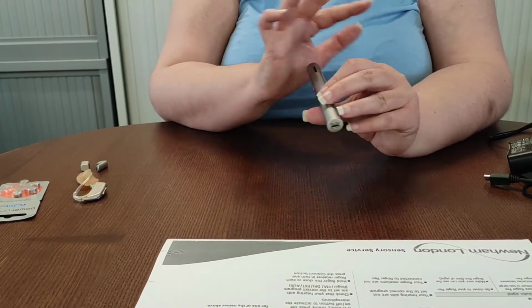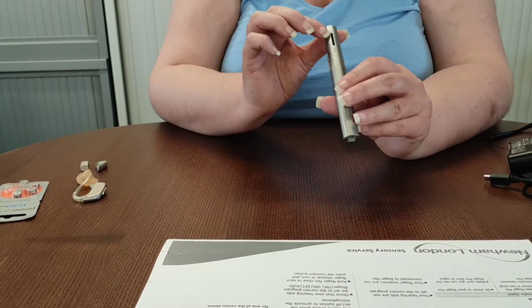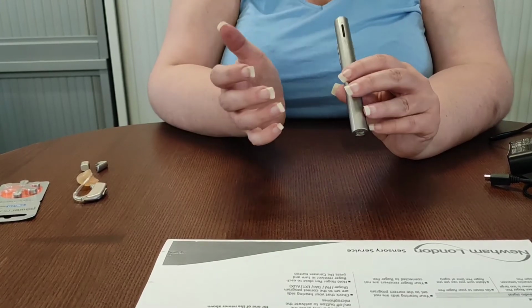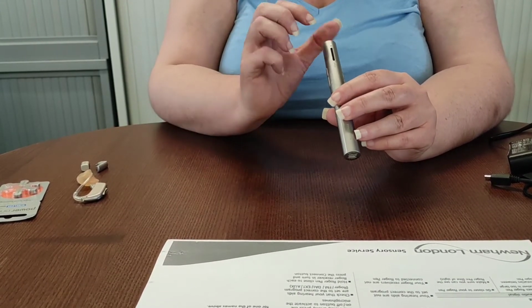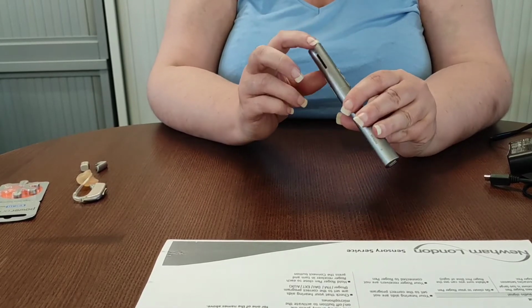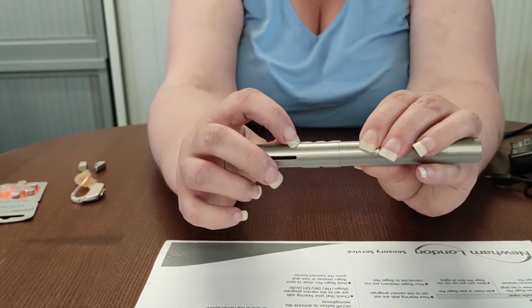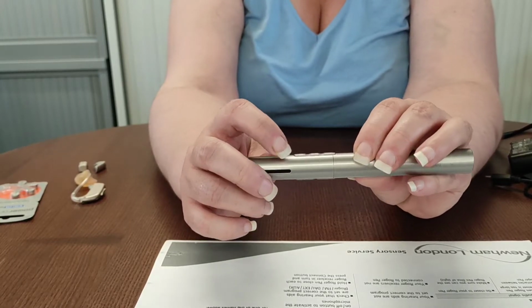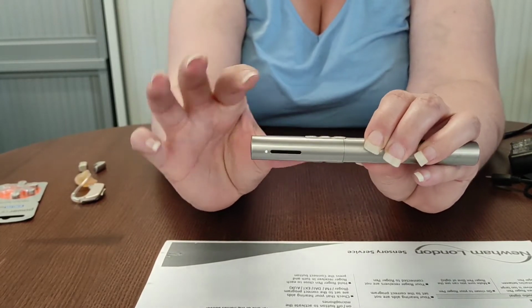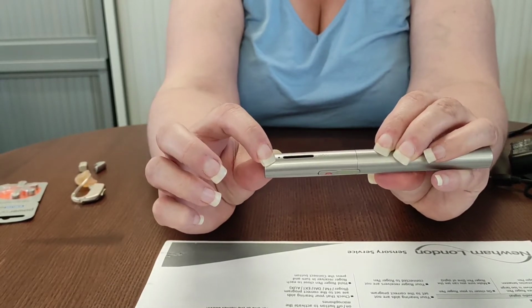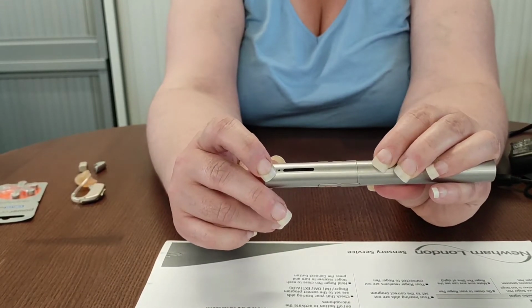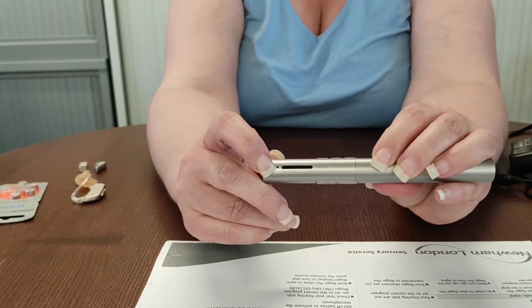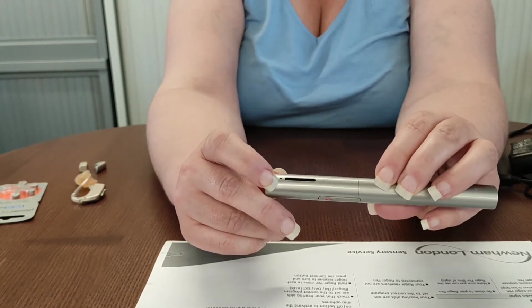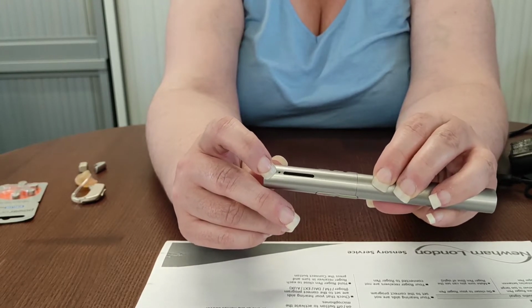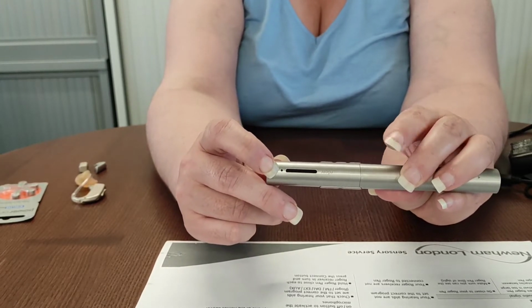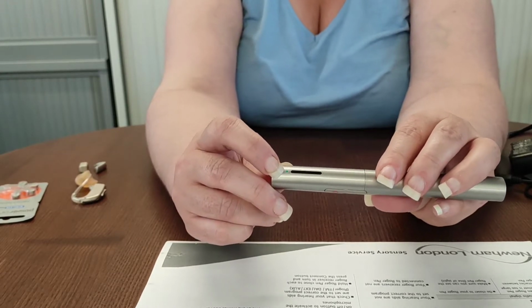Now, we're going to look at some of the functionalities of it and what the lights mean, because this is a key point of this device. It doesn't have a display screen like other versions that tell you what's happening. You have to know about the lights. So let's get going with that. So on the side, you'll notice there is the classic symbol for an on-off. So we're going to press that and hopefully you should be seeing a green light. Now that's solid to start with, which tells me that it's fully charged. And now it is blinking on and off green, and this tells me that the device is working. Now, if you see this blinking light change from green to a red blinking light, that means the battery is extremely low and you need to put it on charge straight away.